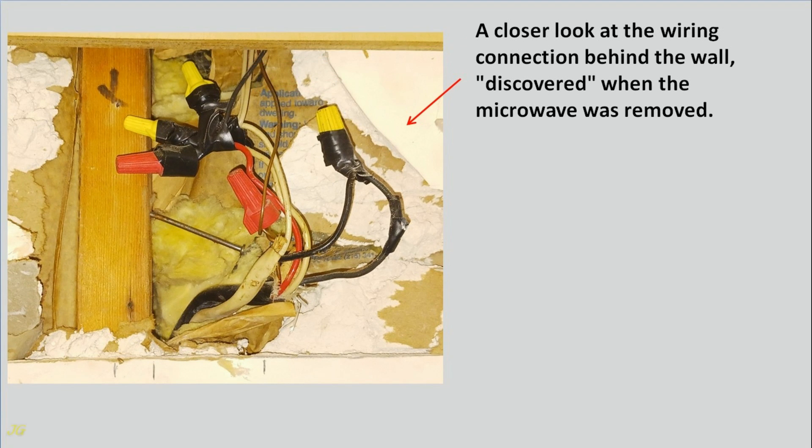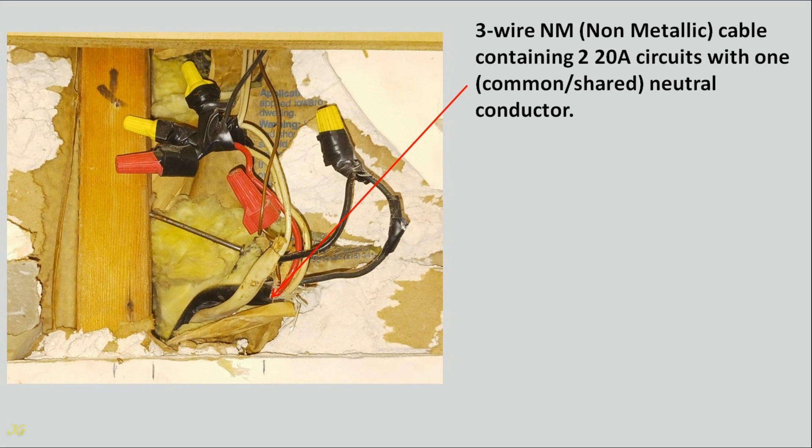A closer look at the wiring connection behind the wall, discovered when the microwave was removed. 3-wire NM non-metallic cable containing 2 20-amp circuits with one common shared neutral conductor.